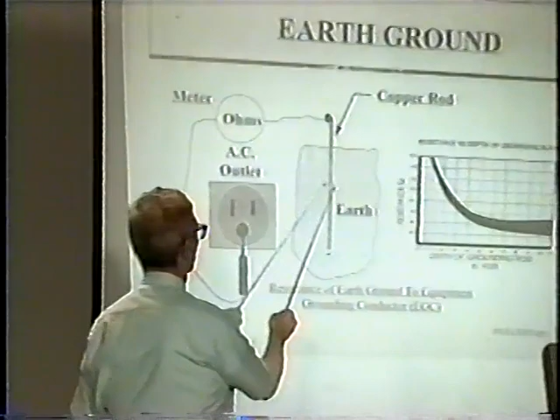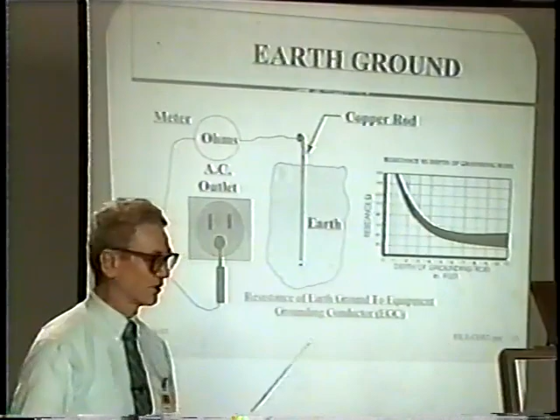What we do at a workstation is use the third wire ground as the ground point to establish equal potential at the workstation, and this is connected back through earth where the power company supplies the incoming power at the building.